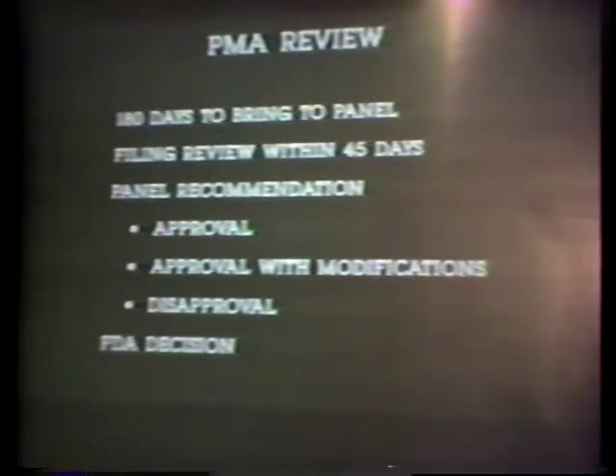In a PMA, FDA is looking for clinical utility and sound scientific data that support the claims made for the product. Submissions will not be approved that do not provide valid scientific evidence of effectiveness and that do not clearly demonstrate clinical utility. Clinical utility can be interpreted to mean that the device provides a beneficial therapeutic effect, or for a diagnostic tool, that it provides information that measurably contributes to a diagnosis of disease or condition. It is not sufficient to establish that the device functions in accordance with its design.